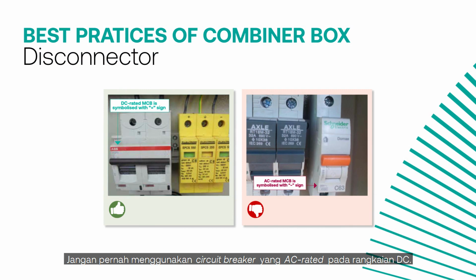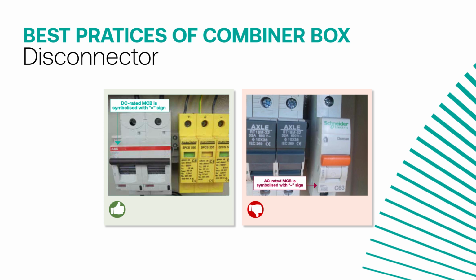Never use an AC rated circuit breaker in a DC circuit. Only use a circuit breaker labeled as DC rated for DC application. Pay attention to the DC and AC sign to distinguish a DC rated and an AC rated switch. Use the correct rating of the switch.